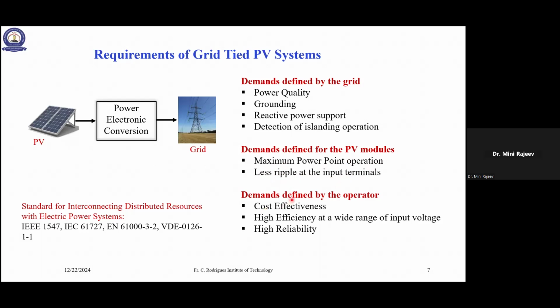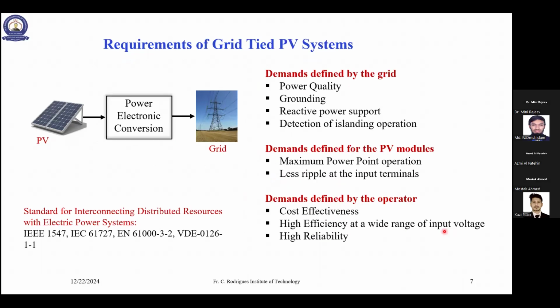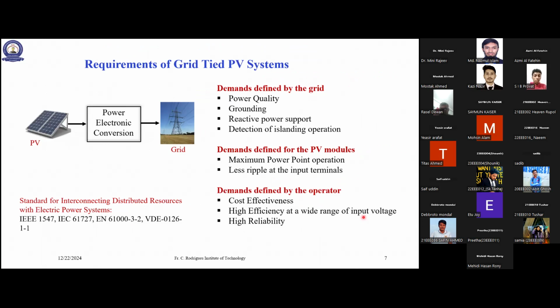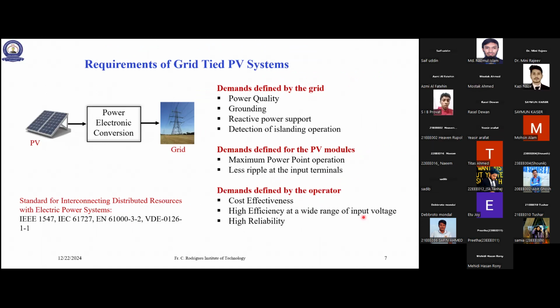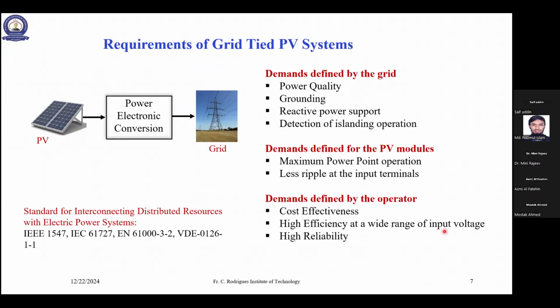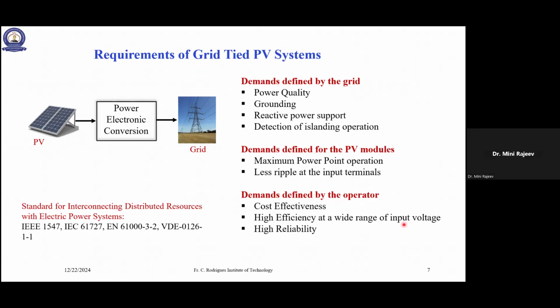Then of course, demands defined by the operator like us: cost effectiveness. We don't want to pay more. High efficiency at a wide range of input voltage, because the solar panel operates over a wide range, as it is affected by intensity of light and also by temperature. So your efficiency should hold for that range of input voltage. Then high reliability. The power we are getting should be reliable. So these are the requirements of the grid-tied PV systems.